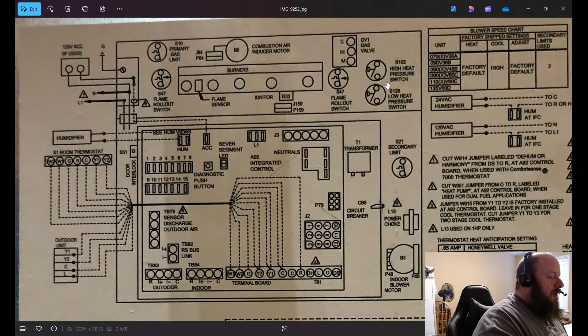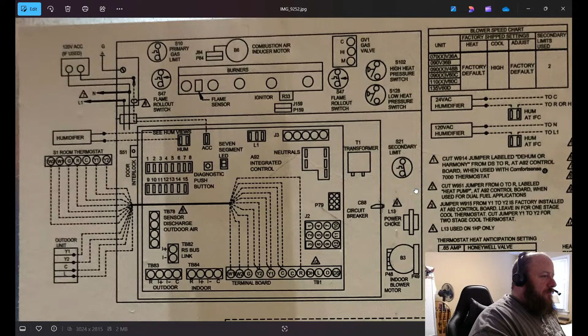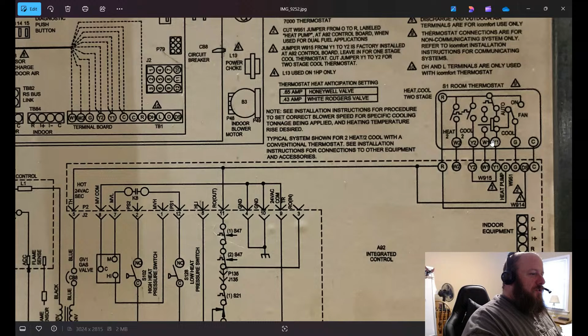All right. So just because it's a temperature or pressure switch doesn't mean it's designated for heat pumps or ACs or gas. They're all the same. Just a matter of what they're doing. Then you go down here to S21 below the high and low. You have a secondary limit, another temperature switch. Go over here to the right in the middle of the screen. Room thermostat. 1, 2, 3. Temperature switches. Fan auto on. Single pole, double throw. Auto or on. So you can see some of the stuff we discussed is right here in our thermostat alone as well.